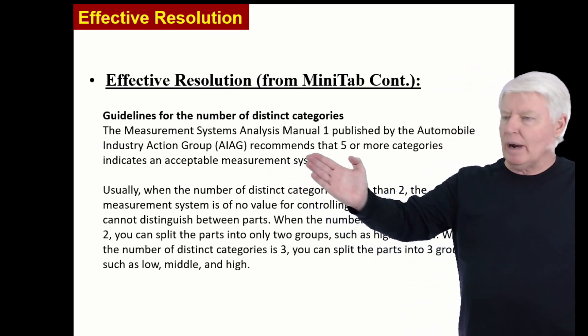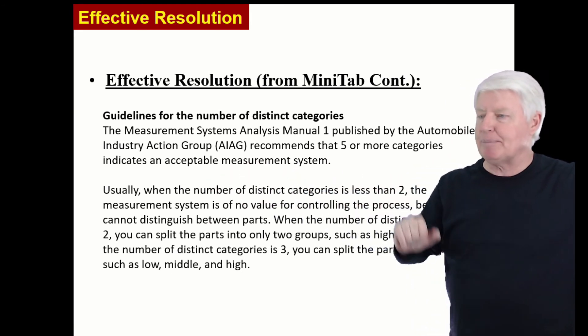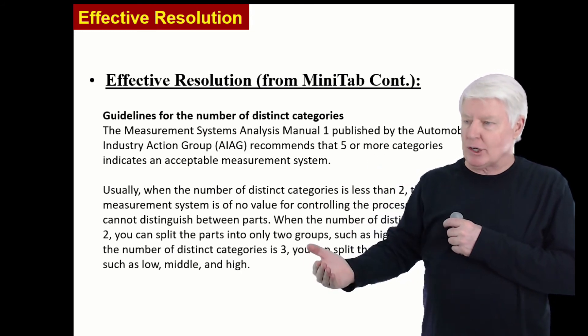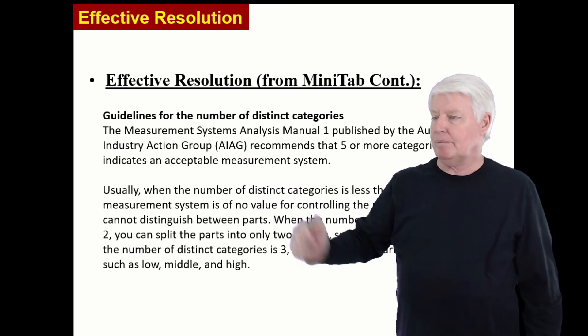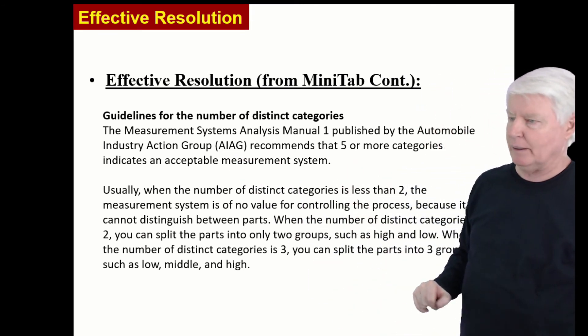So AIAG recommends what? That five or more categories indicates an acceptable measurement system. So if you're going to say something is measurable from the NDC standpoint, it should be five or greater, according to AIAG. And that's what most companies follow, by the way.